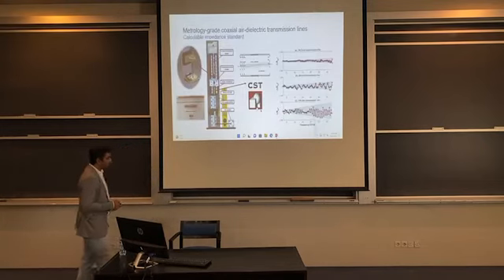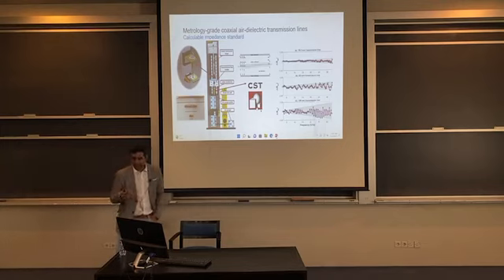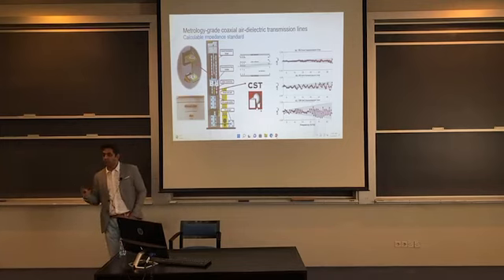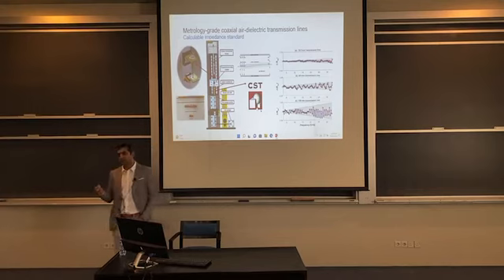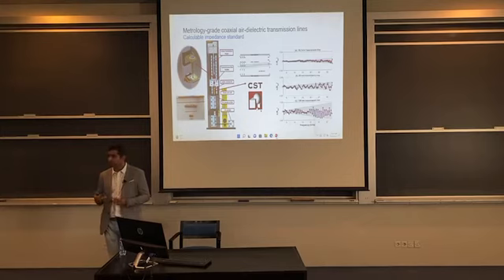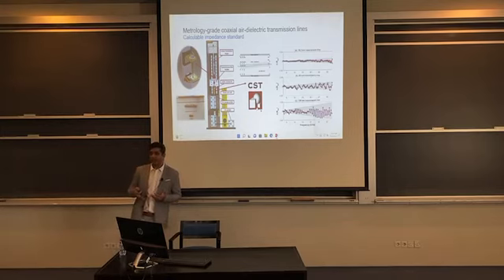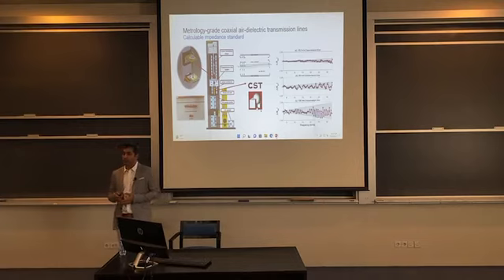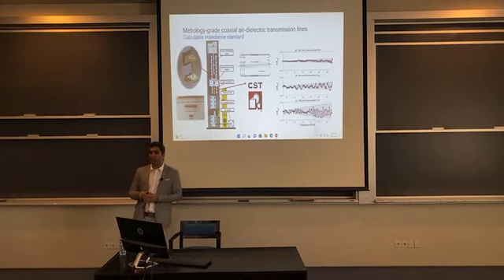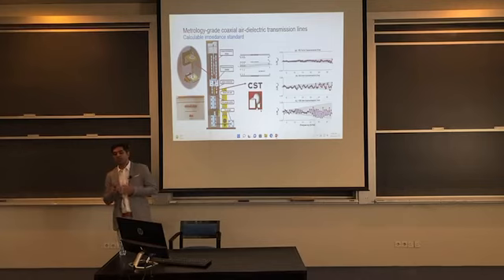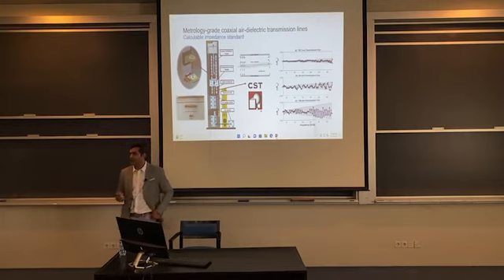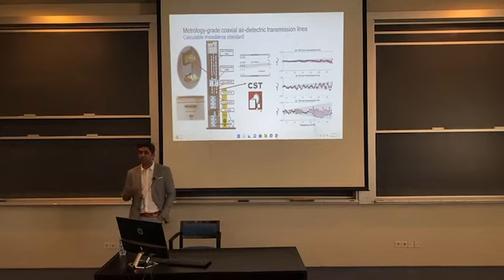So how do we do it for a VNA? A vector network analyzer basically measures two important parameters: impedance and transmission. For impedance, we need coaxial transmission lines, because those are a primary reference standard for impedance - we can measure the dimensions of such a transmission line, and based on those traceable mechanical dimensions, compute the electrical impedance at high frequencies. That information is then used for calibration of a VNA.